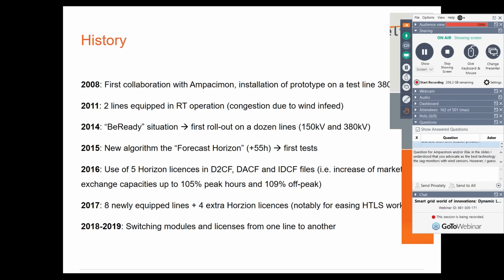Later on came a new product. Also there, we didn't want to install it directly. That was the forecast license. It allows you to have an insight for the 2 coming days over the possible capacity you could have on those lines. And of course, this is really interesting for the market side. If you can increase the capacity of your lines 2 days ahead, this means you have time to implement this on your grid and to give this to the flow-based market coupling or to other systems. You can give this input to the market exchange, and so you can optimize the exchange between the countries, and that's really valuable.